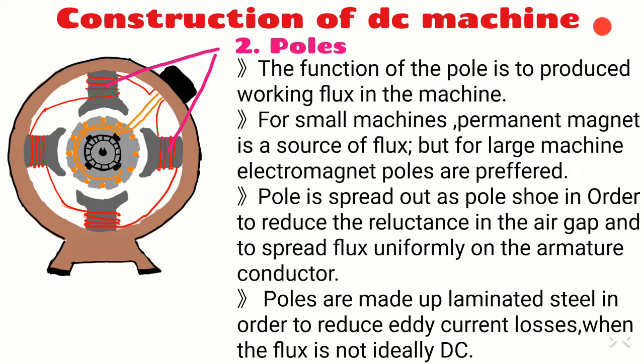The poles have a heteropolar structure with alternate north and south poles. The function of the poles is to produce working flux in the machine. The basic source of flux is a permanent magnet, which is uncontrollable in nature. In order to control the machine, flux needs to be controllable; therefore electromagnets are preferred, which require windings and a DC voltage known as excitation. Excitation is essentially DC because it produces a fixed flux. The pole shoes spread out the flux to reduce reluctance in the air gap and spread flux uniformly on the armature conductors. Both poles and pole shoes are made of steel laminations to reduce eddy current losses.